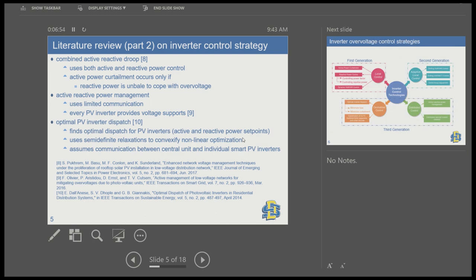The best approach is optimal PV inverter dispatch. It finds the exact amount of curtailment necessary for each PV inverter so that the overall total energy curtailment is minimized. It is a centralized approach that assumes sophisticated communication between the central processing unit and all individual smart PV inverters — essentially the optimal solution for inverter control.